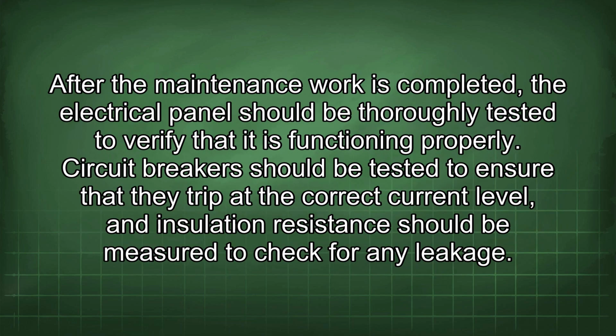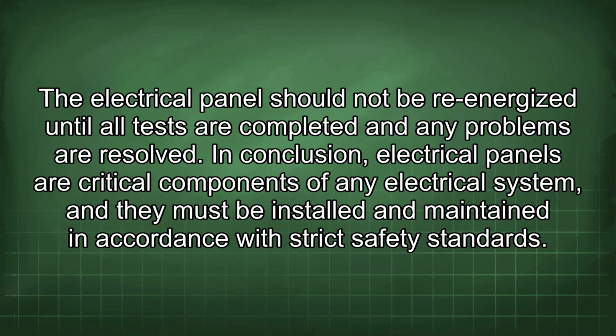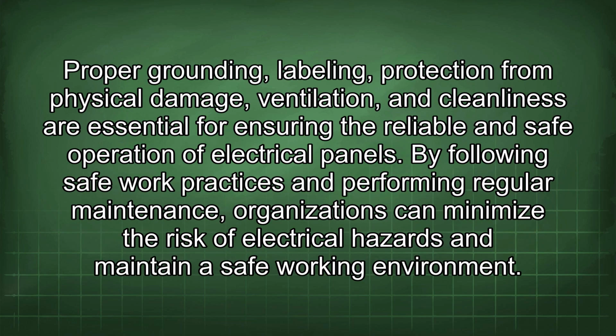After the maintenance work is completed, the electrical panel should be thoroughly tested to verify that it is functioning properly. Circuit breakers should be tested to ensure that they trip at the correct current level, and insulation resistance should be measured to check for any leakage. The electrical panel should not be re-energized until all tests are completed and any problems are resolved. In conclusion, electrical panels are critical components of any electrical system, and they must be installed and maintained in accordance with strict safety standards. Proper grounding, labeling, protection from physical damage, ventilation, and cleanliness are essential for ensuring the reliable and safe operation of electrical panels. By following safe work practices and performing regular maintenance, organizations can minimize the risk of electrical hazards and maintain a safe working environment.